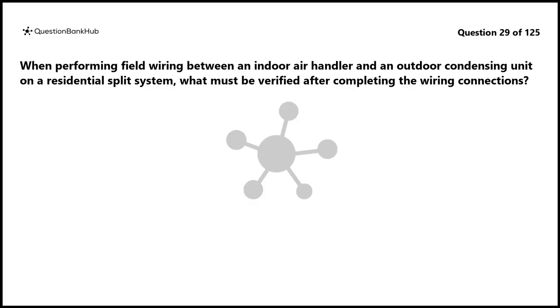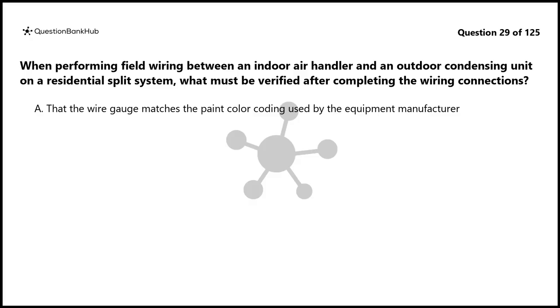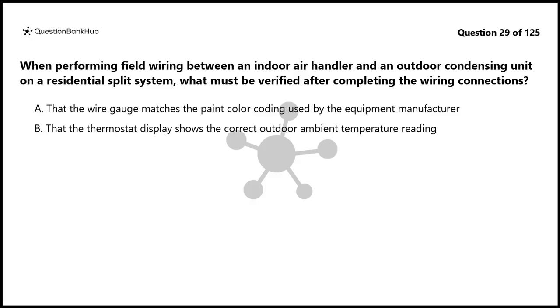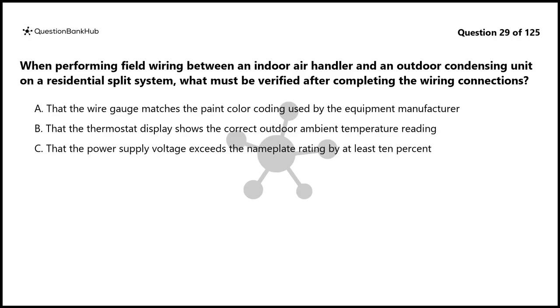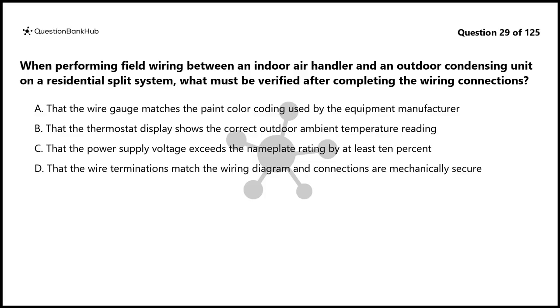Question 29. When performing field wiring between an indoor air handler and an outdoor condensing unit on a residential split system, what must be verified after completing the wiring connections? A. That the wire gauge matches the paint color coding used by the equipment manufacturer. B. That the thermostat display shows the correct outdoor ambient temperature reading. C. That the power supply voltage exceeds the nameplate rating by at least 10%. D. That the wire terminations match the wiring diagram and connections are mechanically secure.